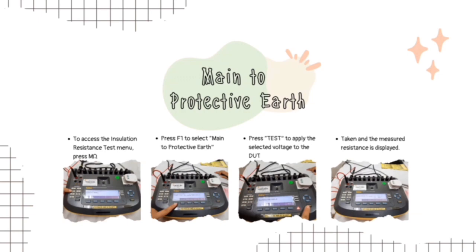For performing an insulation resistance test, we have mains to protective earth. First, press the resistance test menu and press M ohm. And then, select F1 to select mains to protective earth. Press test to apply the selected voltage to the DUT.